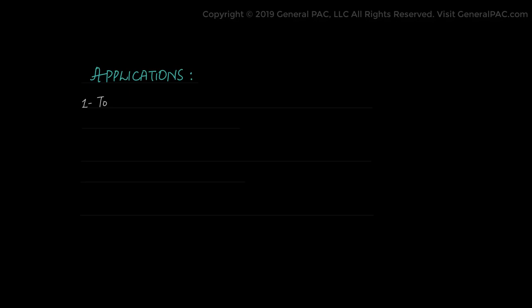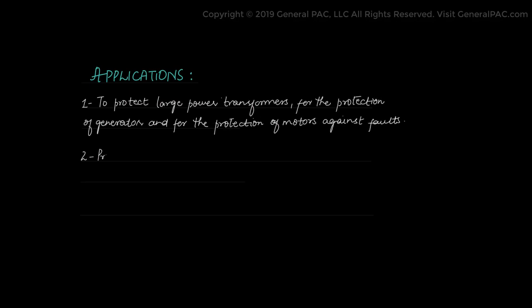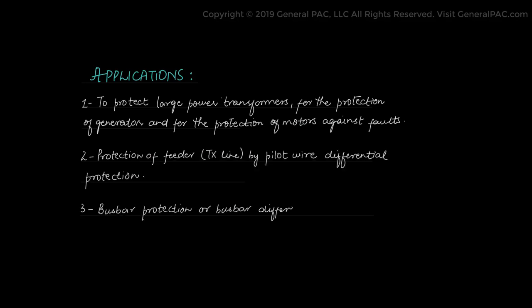Some applications for a current differential relay include protection of large power transformers, protection of generators, and protection of motors against faults and short circuits. Another application is protection of feeder or transmission lines by pilot wire differential protection, or communication assisted differential protection. Another application is bus bar protection or bus differential protection.